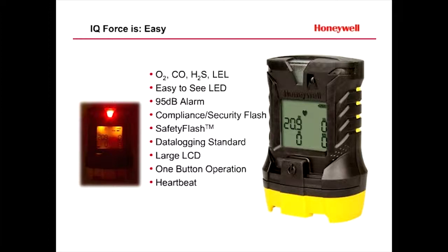Now, another way to configure this LED is to do the exact opposite. Maybe you only want to see the red light flashing when there's an issue, so it's more like exception reporting. In this case, we've got a feature called Safety Flash that monitors the compliance status of the instrument and does a quick double flash of the red light when you've exceeded your bump or calibration intervals.